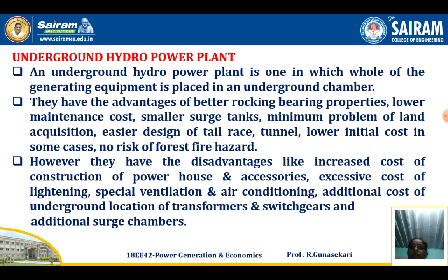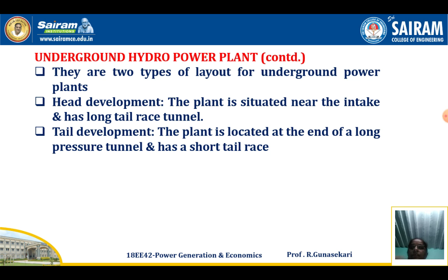However, they have disadvantages like increased cost of construction of the powerhouse and accessories, excessive cost of lighting, special ventilation, air conditioning, additional cost of underground location of transformers and switchgears, and additional surge chambers. These are the disadvantages of an underground hydropower plant.